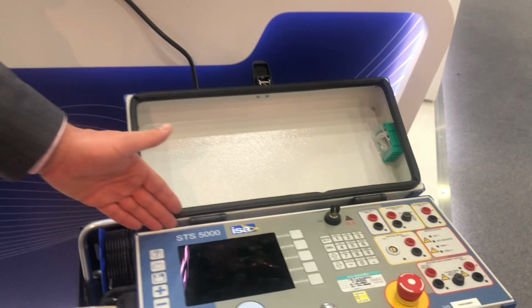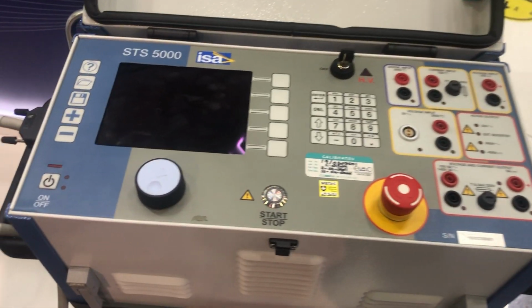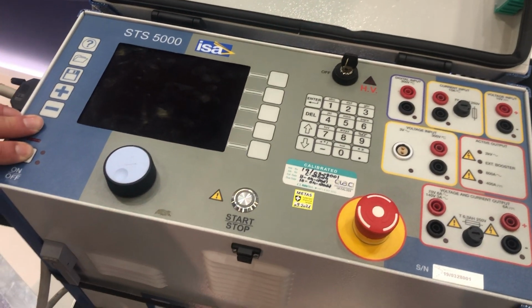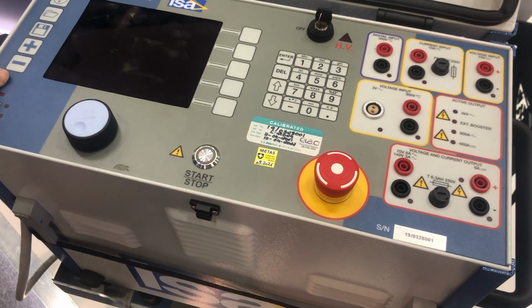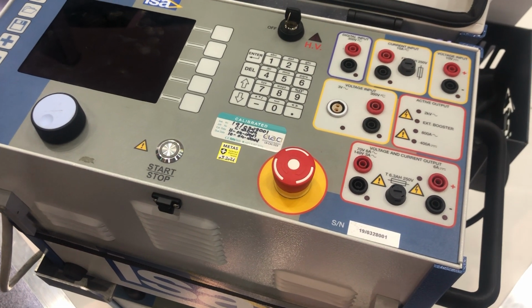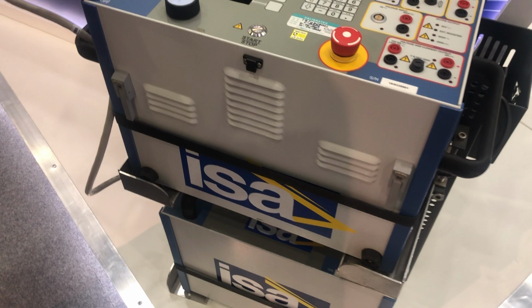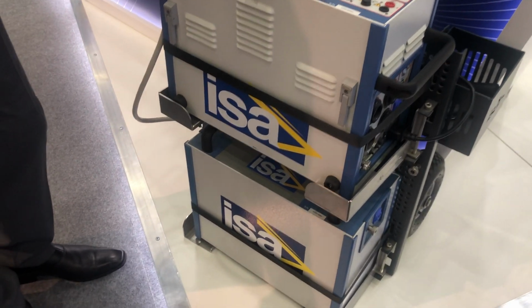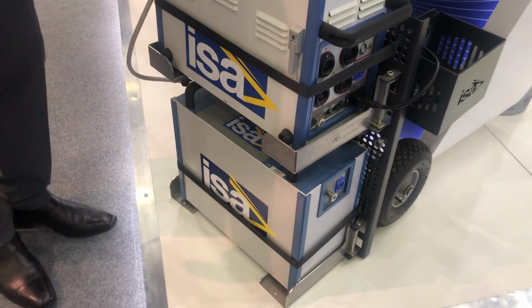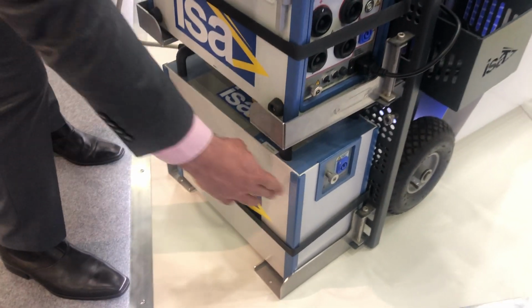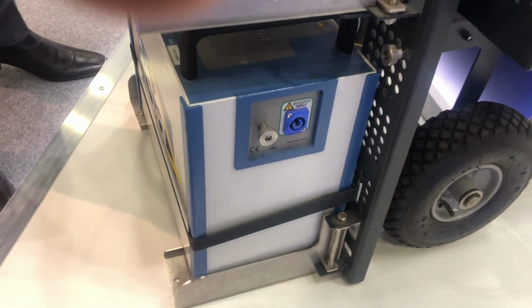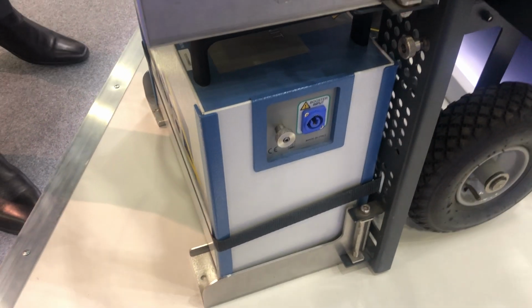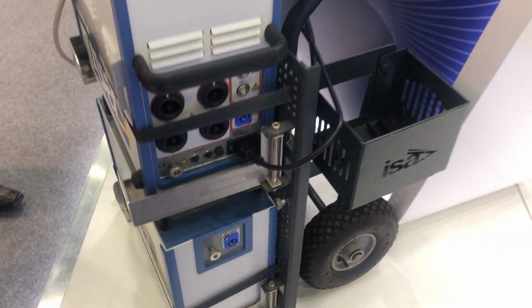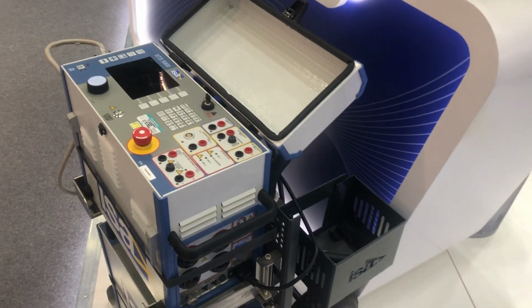Then we have the STS5000. The STS5000 is a substation test set which is used to test the power transformers, current transformers, and voltage transformers. With some additions, you can also test line impedance and step and touch voltage and ground resistance. With the addition of TD5000, you can also do a tan delta test. You can see it mounted on a trolley here so that you can easily move it around the substation.